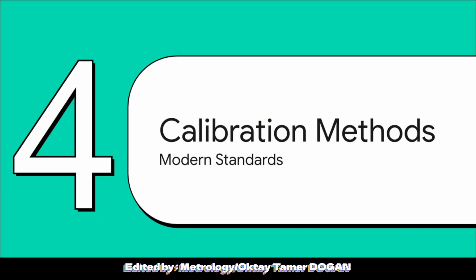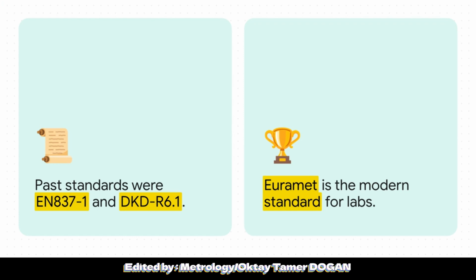Which brings us to Section 4, Modern Calibration Methods. Having the right equipment is really only half the battle. To guarantee safety across global industries, metrologists need some incredibly strict rules. And those calibration rules have definitely evolved over the years. Initially, labs relied heavily on the older EN 837-1 standard. Then, by the 2000s, the German DKD-R 6.1 guideline emerged, and that provided a much more robust framework for testing. But today, the modern gold standard used by national metrology institutes is Euramet CG17. This is a highly detailed set of guidelines that dictates exactly how a pressure gauge has to be tested to prove its accuracy without a shadow of a doubt.